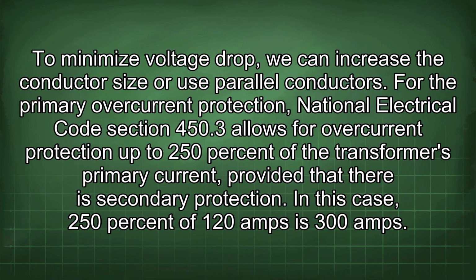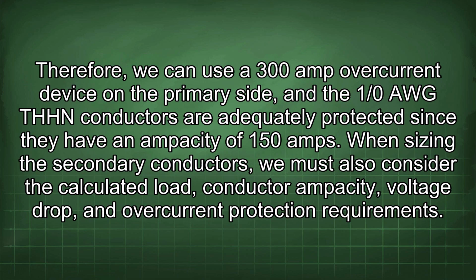For the primary overcurrent protection, National Electrical Code Section 450.3 allows for overcurrent protection up to 250% of the transformer's primary current, provided that there is secondary protection. In this case, 250% of 120 amps is 300 amps. Therefore, we can use a 300 amp overcurrent device on the primary side, and the 1/0 AWG-THHN conductors are adequately protected since they have an ampacity of 150 amps.